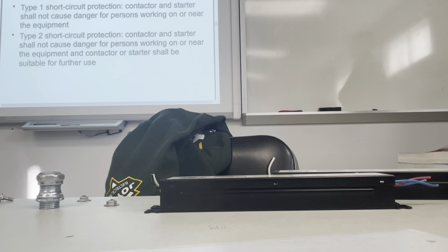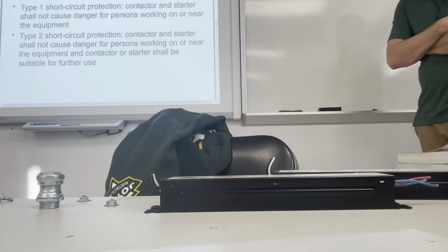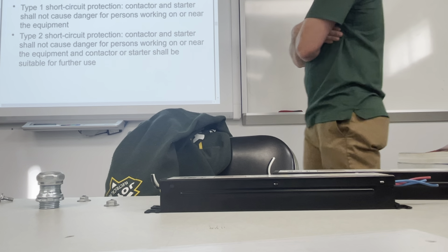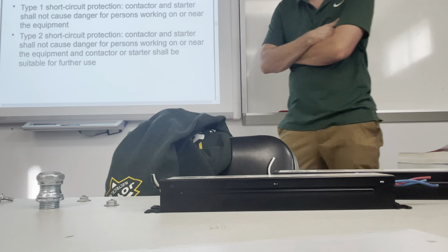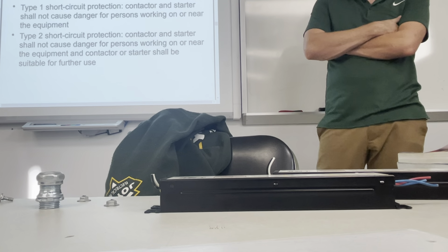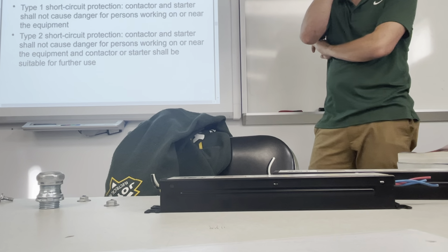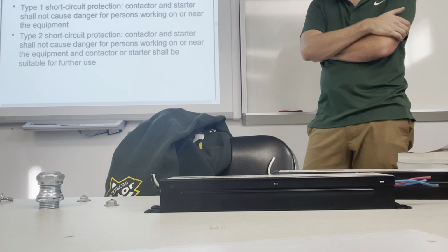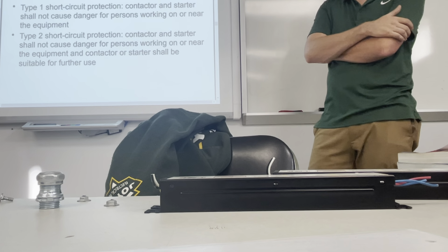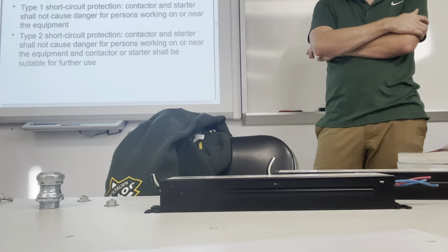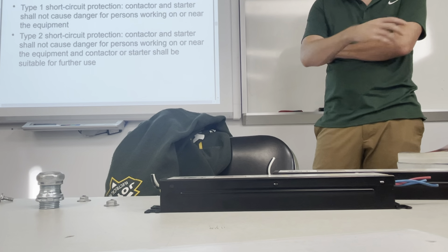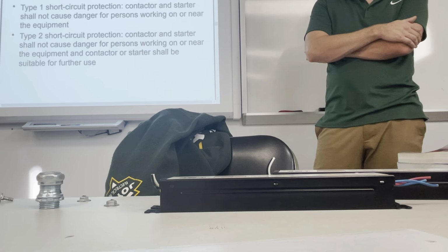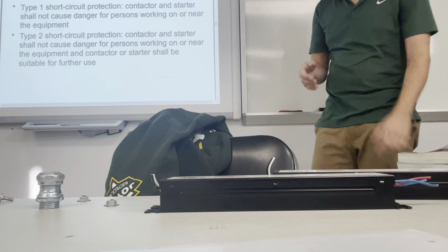So you can just tell by looking at it, it's quality of build, right? Type 1 isn't going to be anywhere near as strong and reliable as Type 2. Type 2 can take a couple of shots. You normally see Type 2 in an explosion-proof kind of environment. Type 1 will just be a standard commercial starter. It doesn't have to protect anything if it fails. Okay, order a new one. It's not going to be the worst thing if this doesn't start right now.